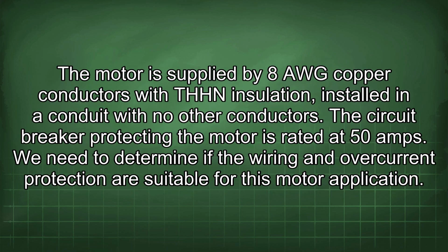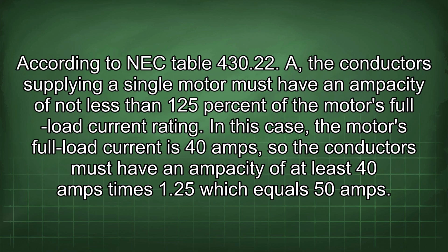The motor is supplied by 8 AWG copper conductors with THHN insulation installed in a conduit with no other conductors. The circuit breaker protecting the motor is rated at 50 amps. We need to determine if the wiring and overcurrent protection are suitable for this motor application.